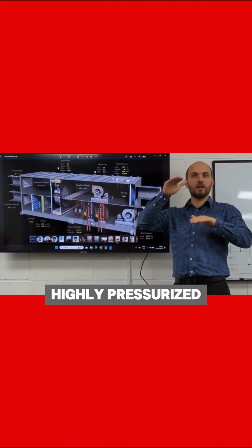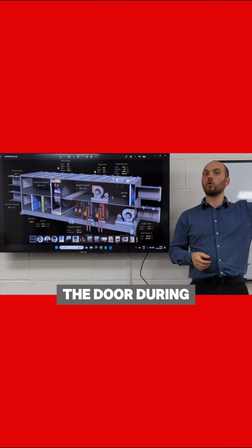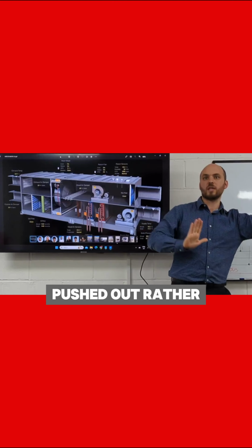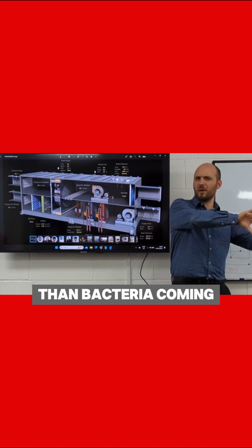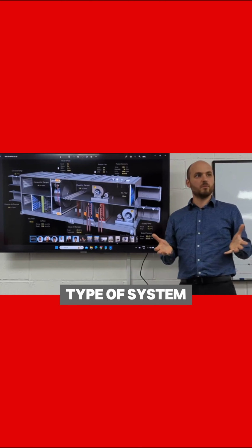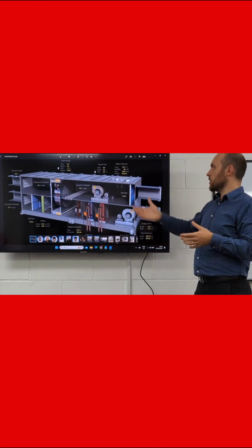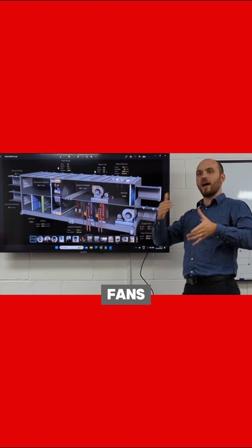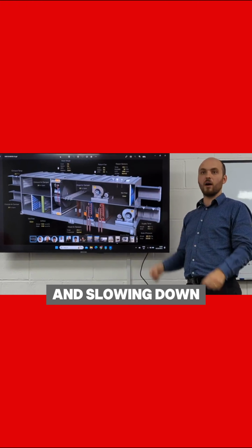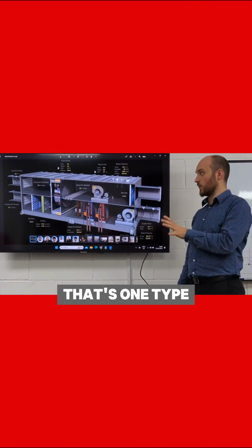It's highly pressurized, so that if the surgeon opens the door during a surgery, the air is pushed out rather than bacteria coming in. So that's a type of system called a pressurized system, where we use a pressure sensor to control the fans. The fans will be speeding up and slowing down based on pressure. So that's one type of control we'll do.